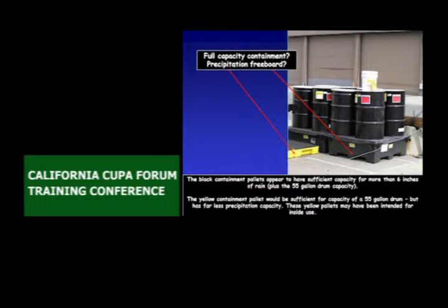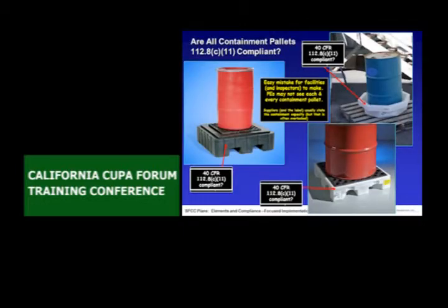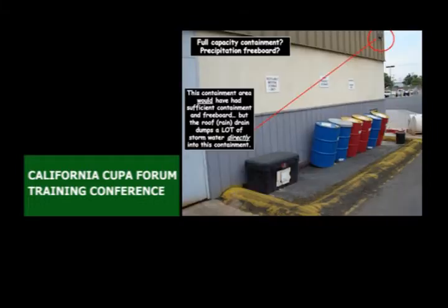This is where inspections count, the right detail on the inspections, implementation, not just what you say in a plan. Anyway, you could buy all kinds of different pallets. Somebody should check the specs. Price is right. Nice containment, right? Has a drain valve. Think, is this adequate for 55-gallon drums? It'll hold 55 gallons, right?